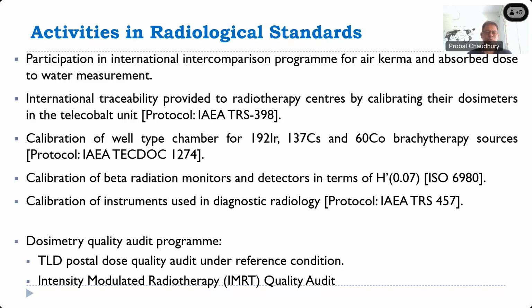Brachytherapy sources are implanted near the affected organ, and they continuously keep giving the dose to get the cancerous cells cured. So brachytherapy is implant based, meaning the sources are implanted into the body. Then calibration of beta radiation monitors and detectors in terms of H-0.07, that is skin dose, as per ISO 6980. Then calibration of instruments used in diagnostic radiology as per the protocol of IAEA TRS 457.